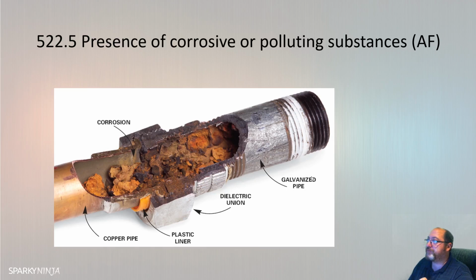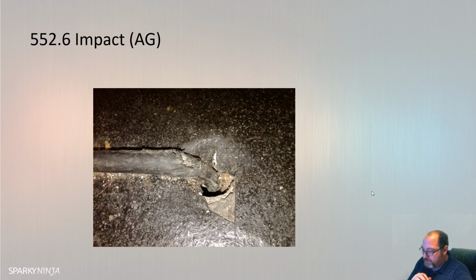Impact. This is actually a picture that I took from a race course that had just been rebuilt, and this was about a month after it had been built. Hostess trolley banging into the cable. It just came out of the ground and fed a socket outlet. Wasn't very good. Impact then. So this is another external influence.